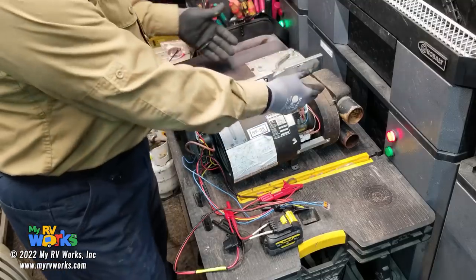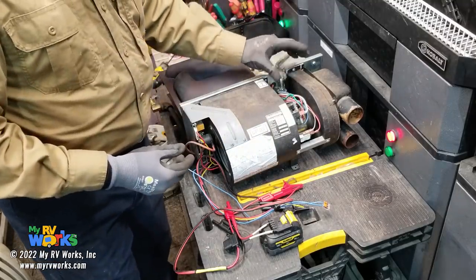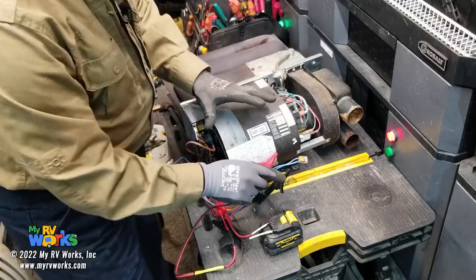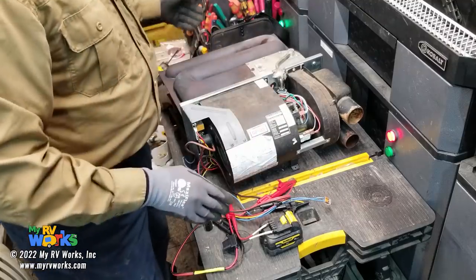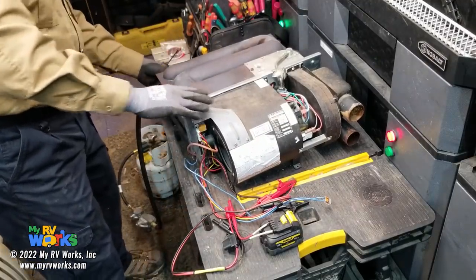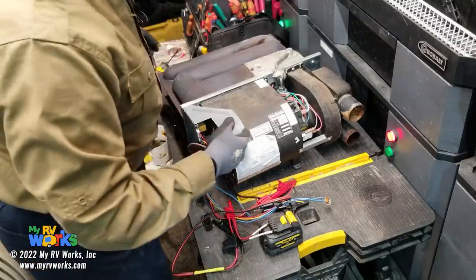It would work like this for a while and then you would hear the gas solenoid opening and closing, opening and closing. Now, if you understood everything I just went over, what would cause that? Well, certainly this high temperature switch. So watch, I'm gonna unplug this right here. There, I just unplugged the wire on the back.